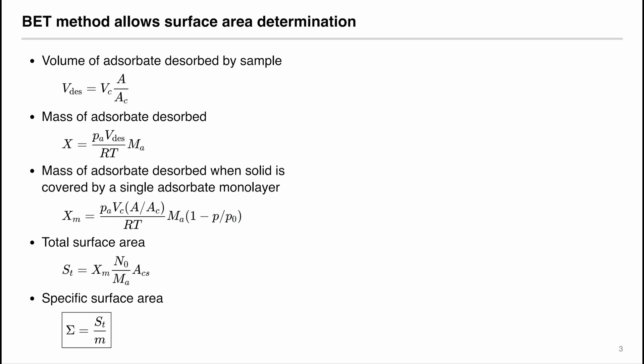The volume of adsorbate desorbed by sample V desorption equals V of c, which is the calibration volume, multiplied by A divided by A of c, where A is the sample integrated reading and A of c is the calibration integrated reading. These are measured by the instrument.